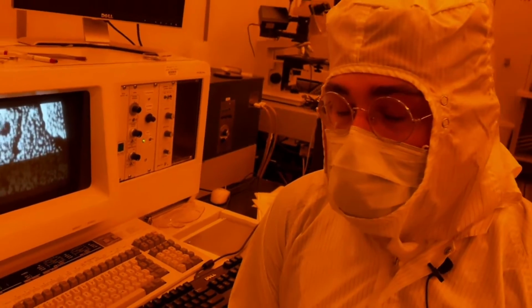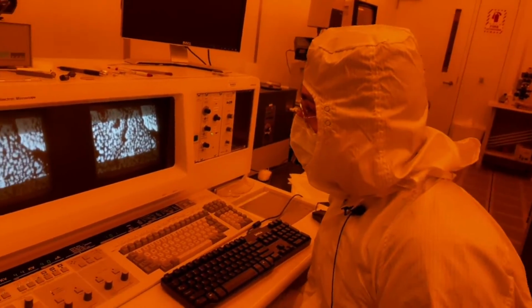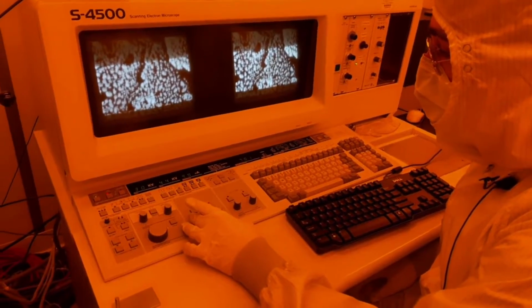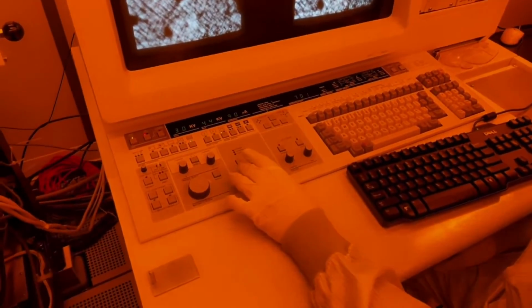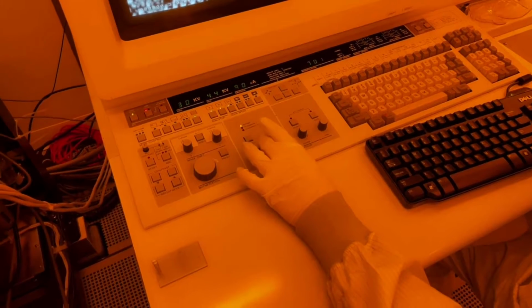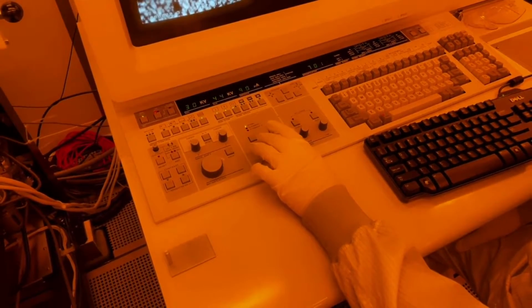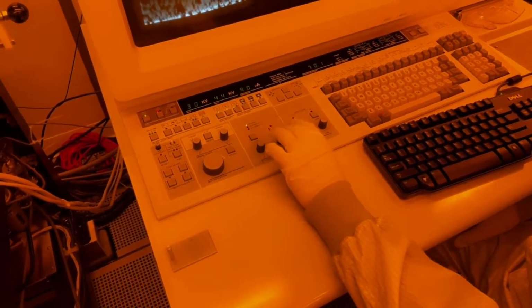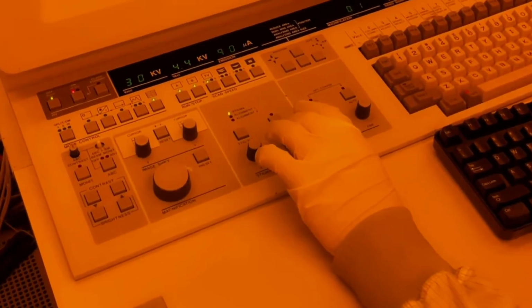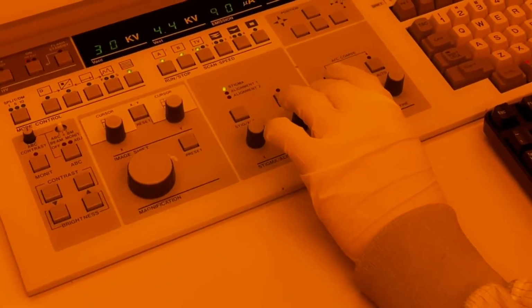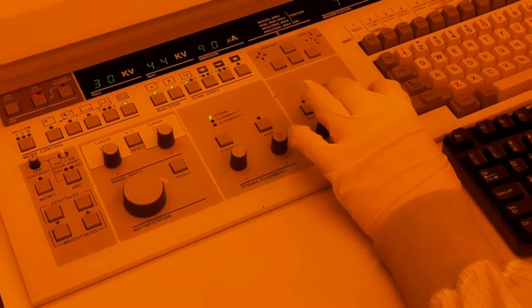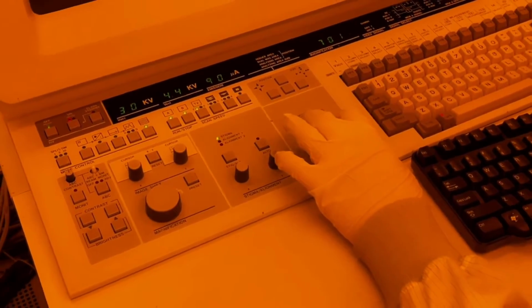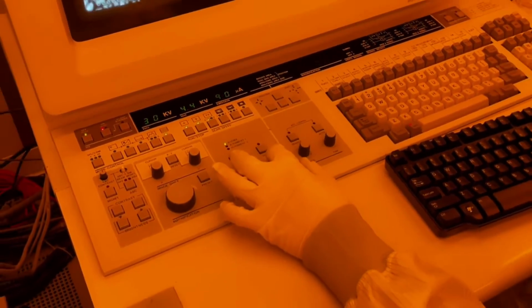The reason this happens is because of stigmation. Stigmation occurs when the electron beam is an oval, rather than a circle like it's supposed to be. To correct that, we have these two stigmation alignment knobs, and basically the way that you're going to approach this is you're just going to go back and forth. So you're going to use your stigmation knobs to get the best image that you can. Once you do that, you're going to go back to your fine focus. Do fine focus again, and then go back and forth.